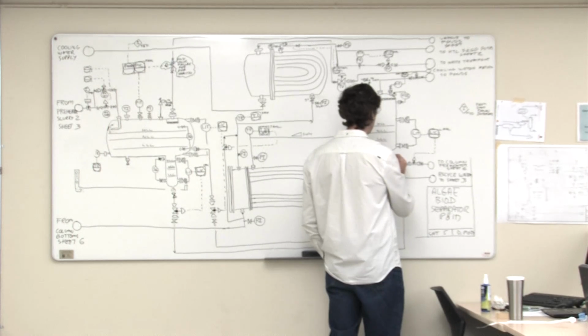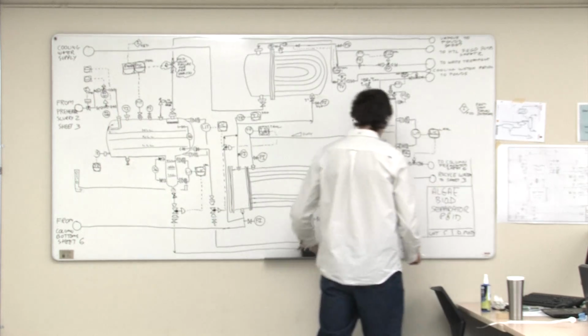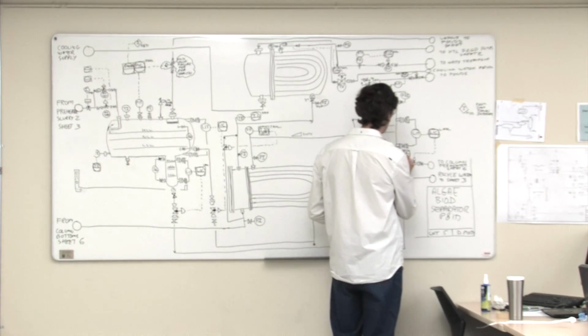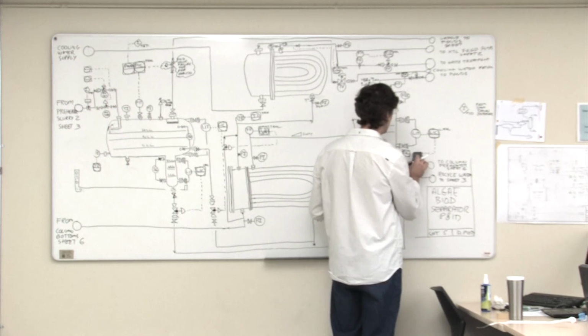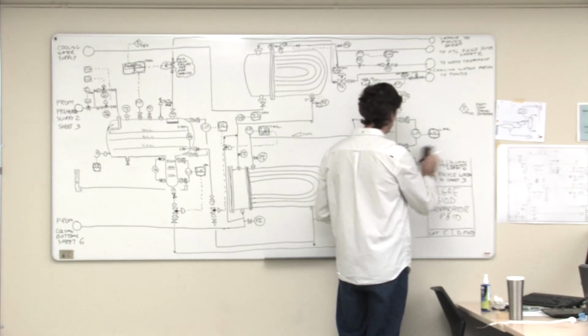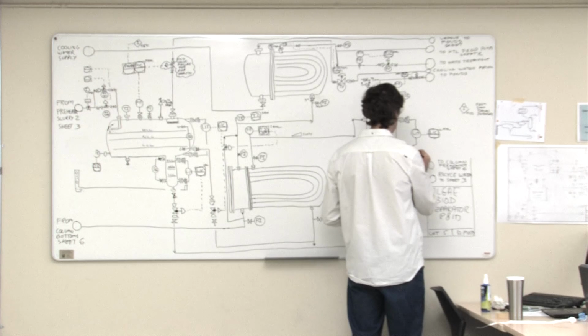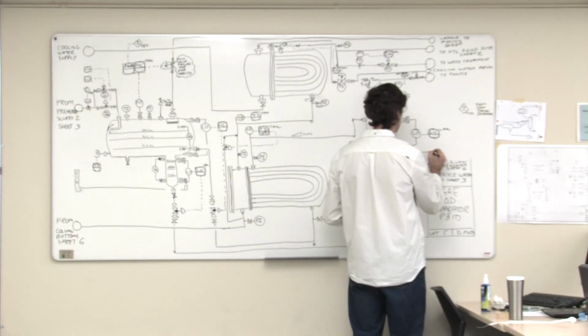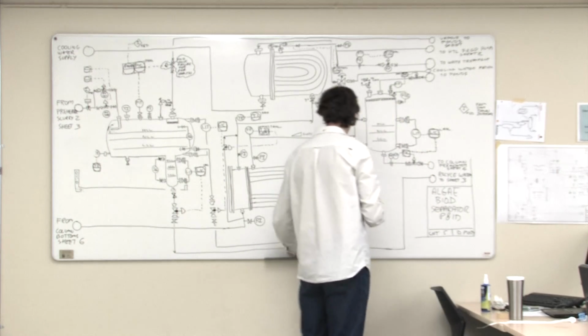So that's easy. Put an FE in and an FIT. And then we'll put an FIC in, like that. Yeah, this is actually not a bad idea. And the level controller now has to send a signal into the flow controller, and because it's all internal to the DCS, it's going to be done with software. So I get rid of the dash line, and I use dash dot. Dash circle, actually. And then the flow controller becomes the interior.